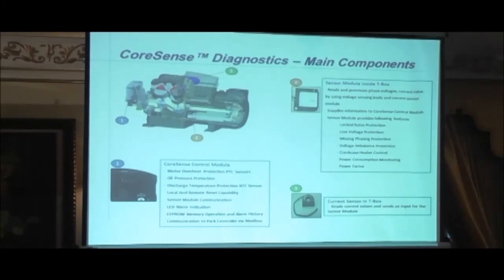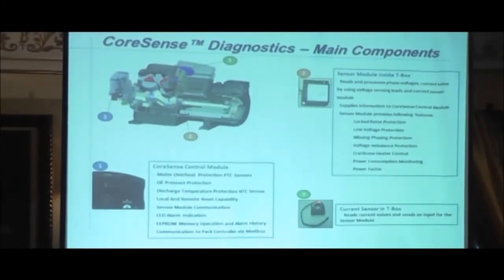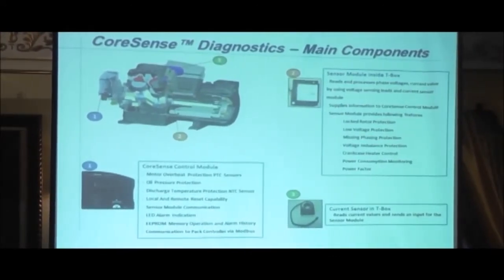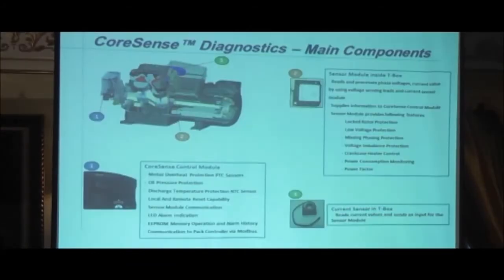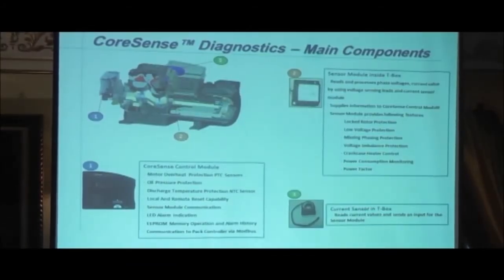So if we look at the main components again, here we have the control module. This is mounted externally. And we have these two components that are now mounted inside the terminal box. Okay. We have a current sensor. The sensor is going to measure the current on one of the phases that is drawn by the motor. You can see there's a connection cable here. The connection cable is connected to the sensor module. The sensor module itself will do all the voltage, missing phase, voltage imbalance, power consumption, and so on. Okay. And then this module is connected to the diagnostic module, where this will interpret all the signals and visualize all the LED safeties.